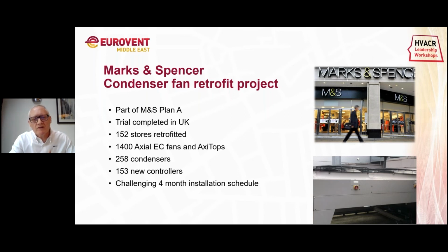So we looked at their refrigeration plant, and it was reasonably efficient, but we noticed they had on-and-off style condensers - literally the fans would just turn on and off as the load required, and the compressors again on and off. So although it was reasonably new, it wasn't controlled particularly well.